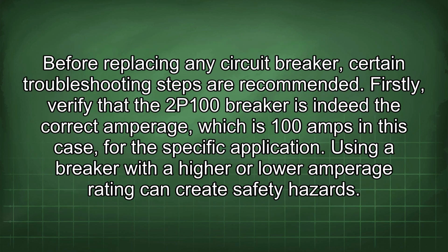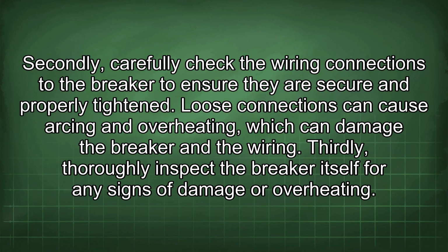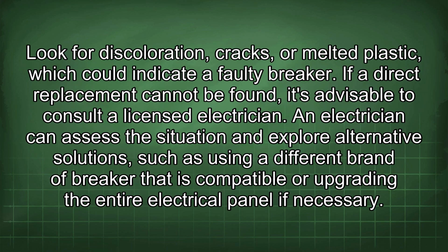Before replacing any circuit breaker, certain troubleshooting steps are recommended. Firstly, verify that the 2-pole breaker is indeed the correct amperage, which is 100 amps in this case, for the specific application. Using a breaker with a higher or lower amperage rating can create safety hazards. Secondly, carefully check the wiring connections to the breaker to ensure they are secure and properly tightened. Loose connections can cause arcing and overheating, which can damage the breaker and the wiring. Thirdly, thoroughly inspect the breaker itself for any signs of damage or overheating. Look for discoloration, cracks, or melted plastic, which could indicate a faulty breaker.